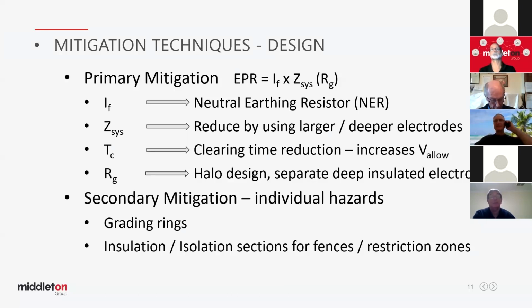There are other ways too. If we can increase our allowable voltage above the hazards we've measured, it's another way to achieve compliance. One of the major inputs to the allowable voltage is the clearing time, as we've seen in previous slides. So we may be able to negotiate with our protection mates, there might be some of us watching here, to see if they can grade their protection to give us a faster clearing time for the particular fault that we're addressing, and therefore increase the allowable voltage and potentially get that above the hazards we've measured to achieve compliance.